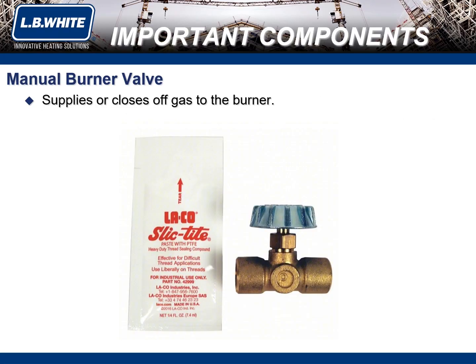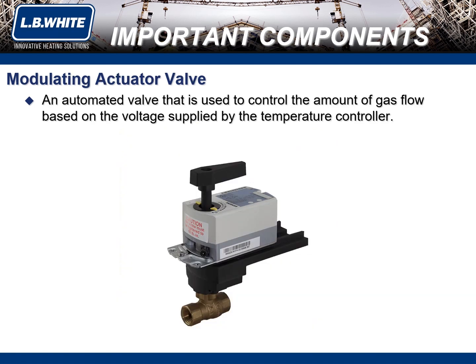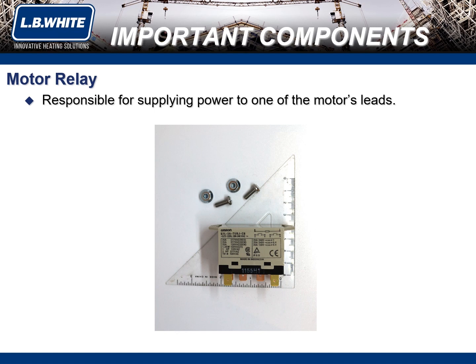A manual burner valve supplies or closes off gas to the burner. A modulating actuator valve is an automated valve that is used to control the amount of gas flow based on the voltage supplied by the temperature controller. A motor relay is responsible for supplying power to one of the motor's leads.